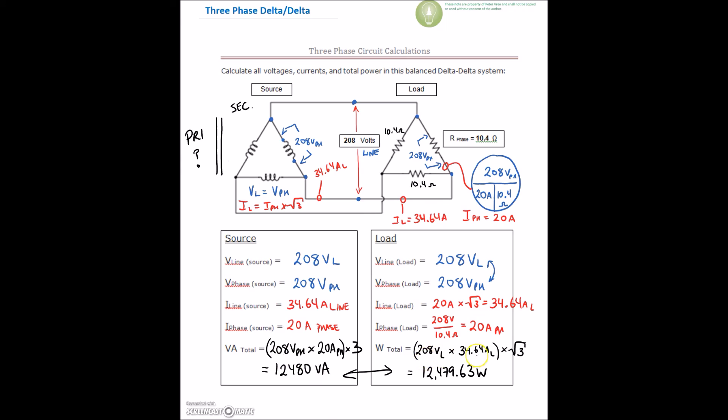In order to find our VA value, we took our line voltage times line current times root 3, and it gave us essentially 12,480. Or we can take our single phase values. 208 volts on the phase times 20 amps on the phase times 3 gives me 12,480 VA.